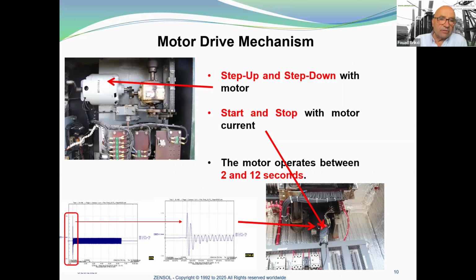On the bottom, you have the recording current that you can see. You have the inrush current, then what we call a plateau for the current, and then it ends with a break. And here you have a zoom of the inrush current. With this, you know exactly whether the sine waves are correct or not. And here you have a picture of the AC current clamp, which is installed on the motor. This way we can record the current.